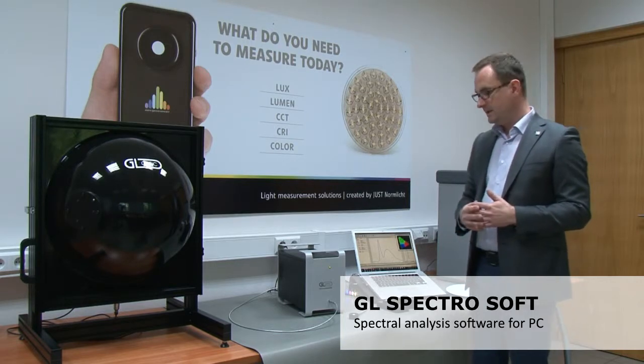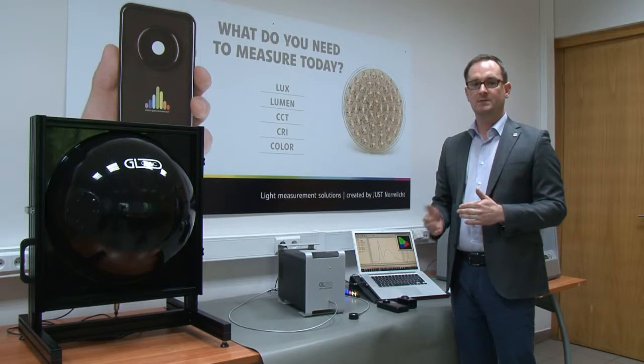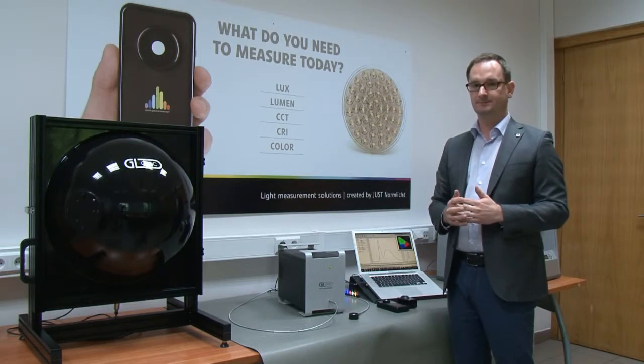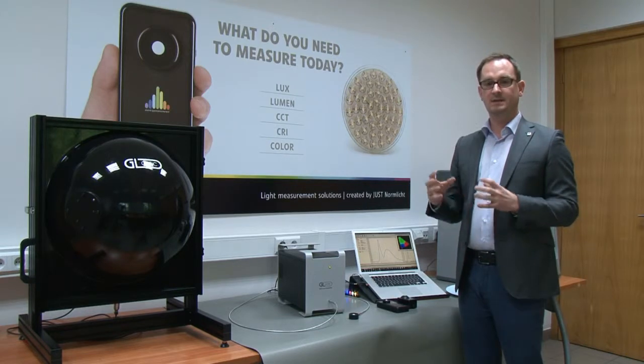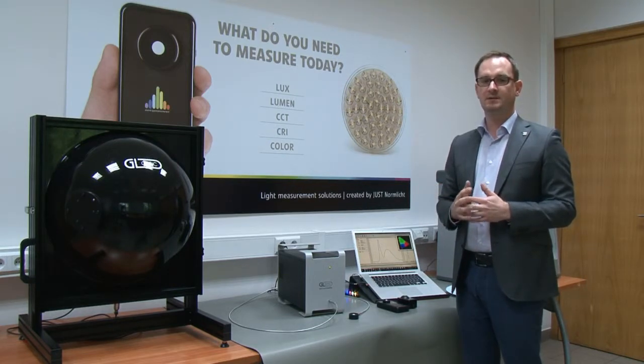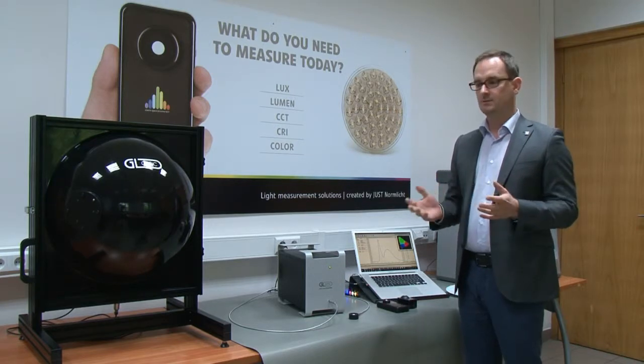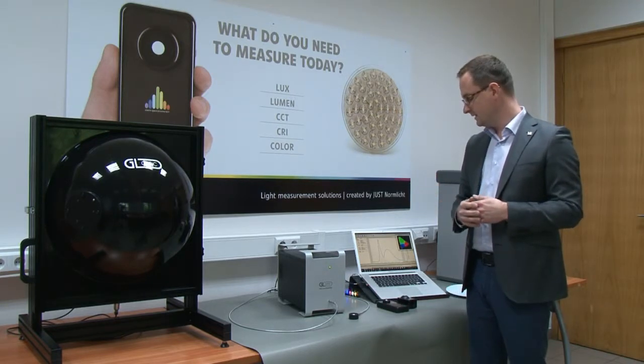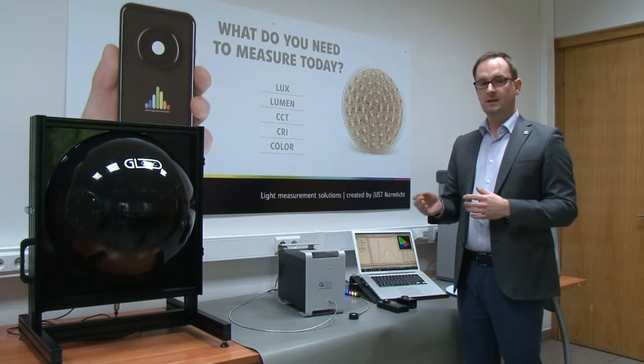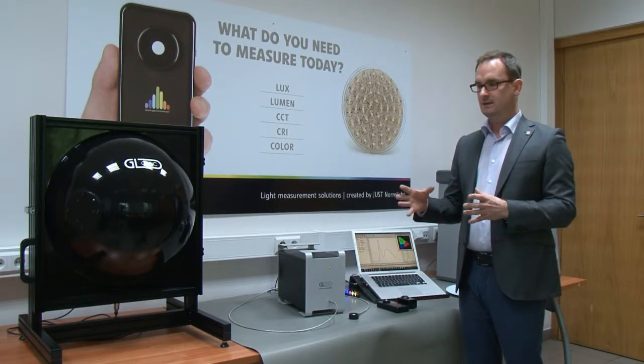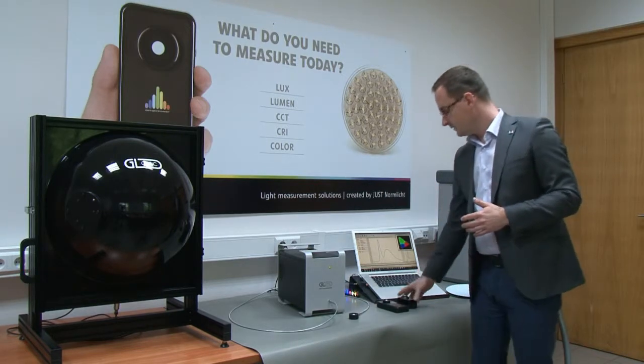Our customers normally work with different sizes of luminaires or different sizes of light sources. Therefore, there is a need for different sizes of integrating spheres if they would like to measure total luminous flux or radiant power of their LEDs — single LEDs, LED arrays, or ready luminaires.